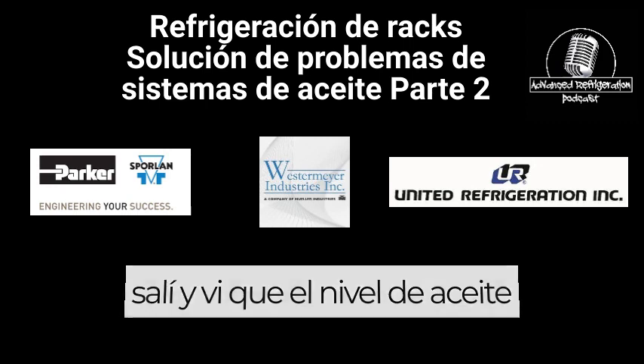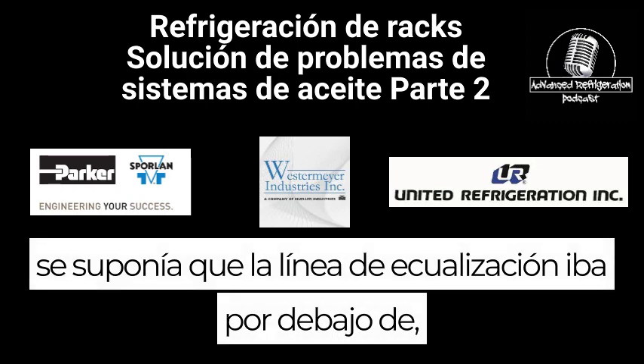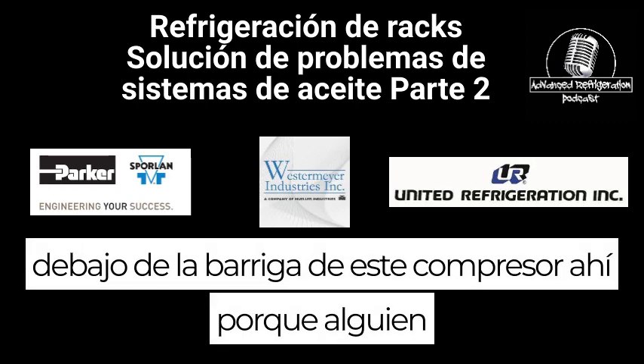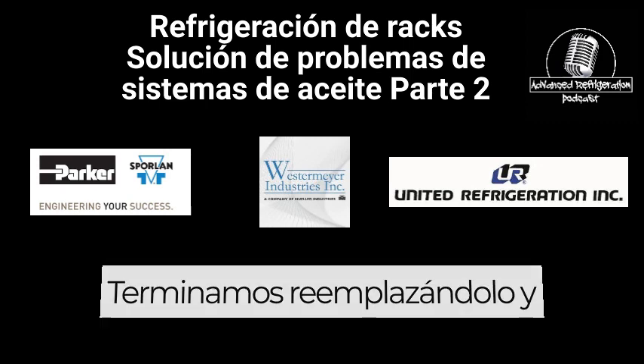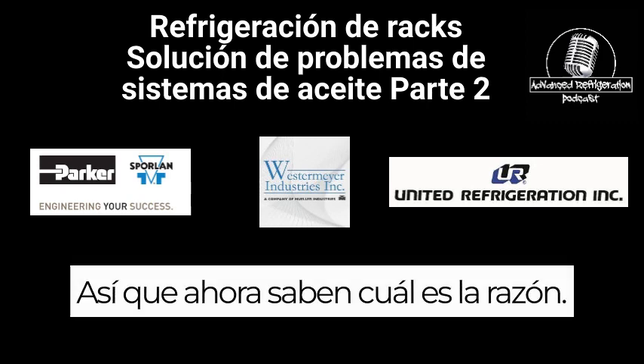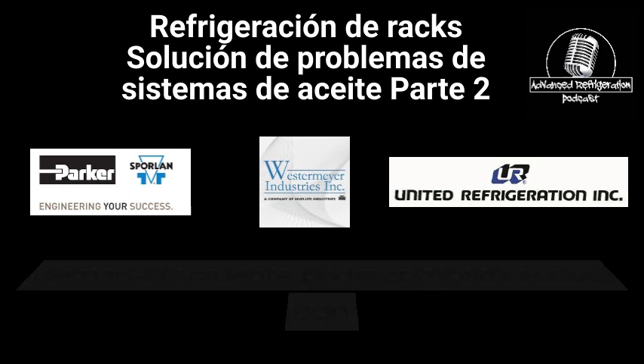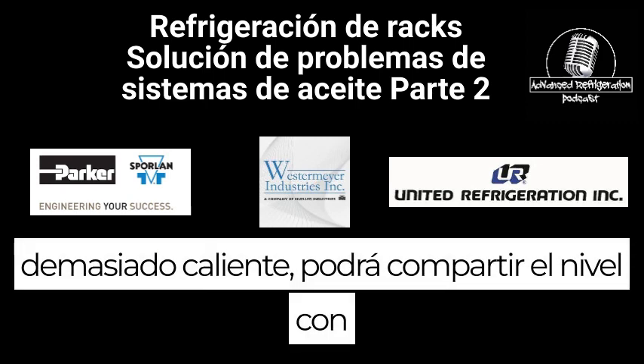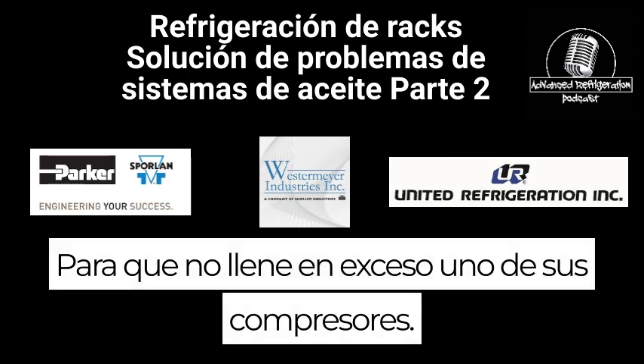It wasn't until I went out there and saw that the equalization line was supposed to go under the belly of this compressor. Someone had removed it thinking they didn't need it. We ended up replacing it and we haven't replaced that compressor since. So now you guys know the reason for it. Like I said, if one compressor fills up too high, it'll be able to share that spare oil with the rest of the compressors, so you don't overfill one of your compressors.